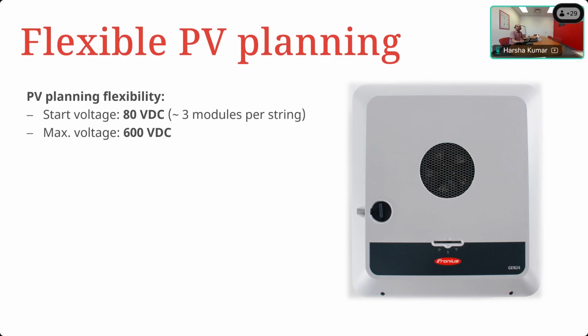Thanks. Okay, now one big difference here compared to the old Primos and the Symos is that the old Primos, despite being single phase, even the 3.8 kilowatt inverter could work up to 1,000 volts DC. That is not the case anymore here. These are all exclusively 600 volt DC inverters, and they were meant as such for residential use. That doesn't per se prevent you from using them on commercial sites if you do need to, or even ground mounts, because we've already seen a few people use them on both, and there's been pretty much no difference there. But this also does give you a bit of an advantage in a different way. I'll come to that when we get to the retrofit side of it.